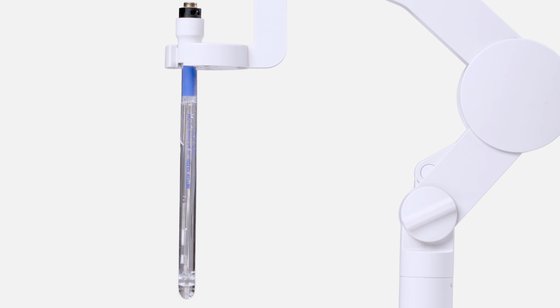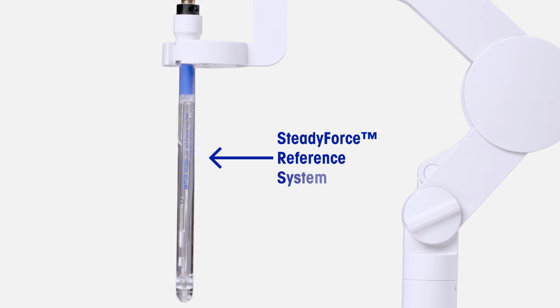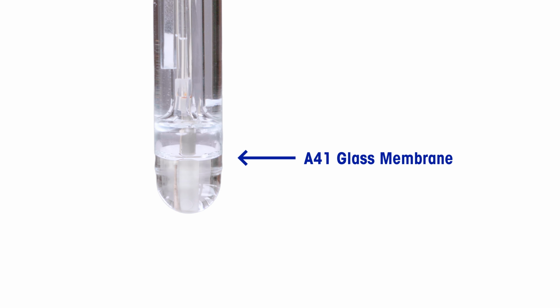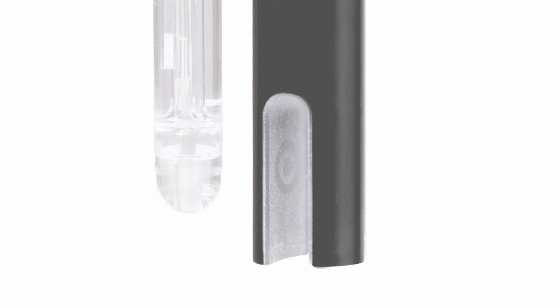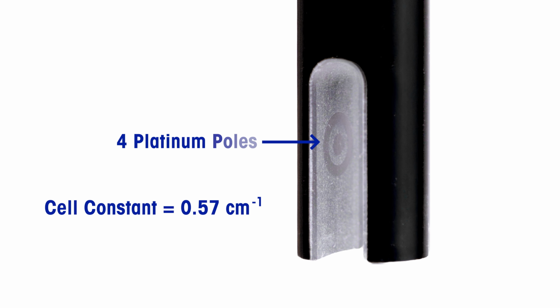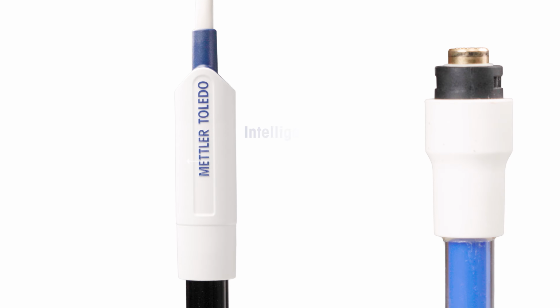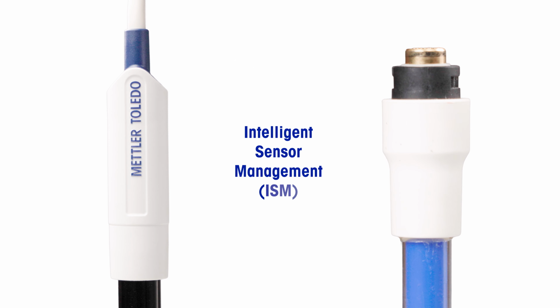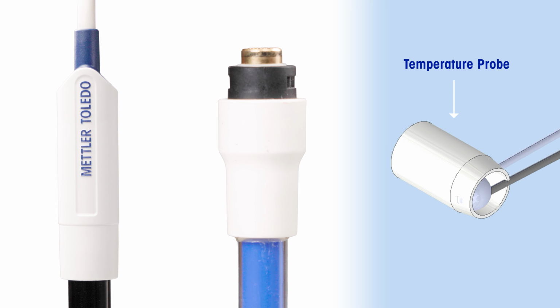Our InLab Power Pro-ISM pH sensor features a steady force reference system that prevents clogging and an A41 glass membrane that can withstand even the harshest conditions. On the other hand, our InLab 731 ISM conductivity sensor has 4 platinum poles with a cell constant of 0.57 cm inverse that provides great linearity over its entire range. Our sensors are distinguished by their ISM feature and integrated temperature probes, ensuring accurate and reliable readings.